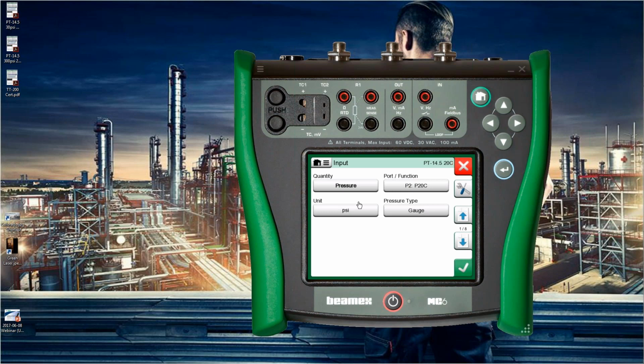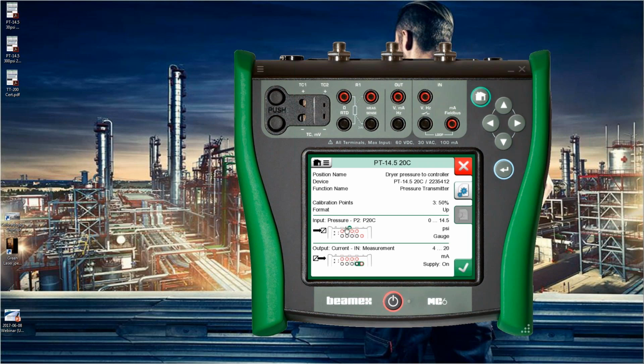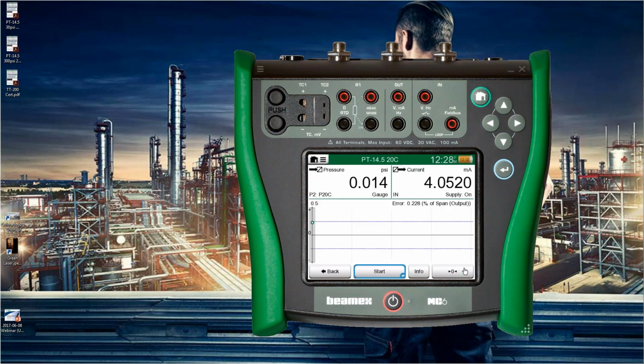Okay, so that's done. And so I'm on the 20C. Let me hit my check mark, and that all looks good. Let me hit check, and I'm going to vent here. I'm hooked up to a different pressure module. I need to make sure to zero that as well, and now I'll hit start. So it still is passing. Now I need to take it up to my midpoint.